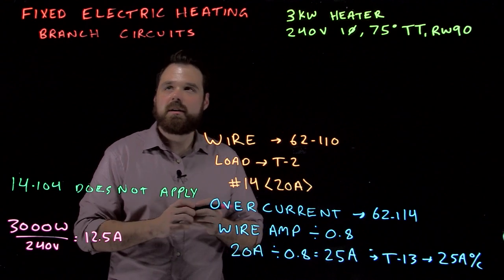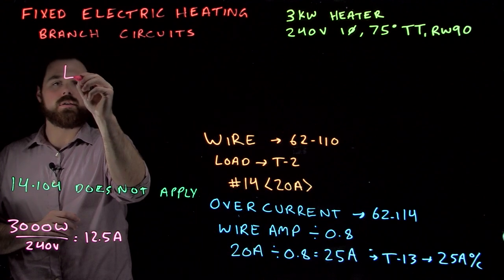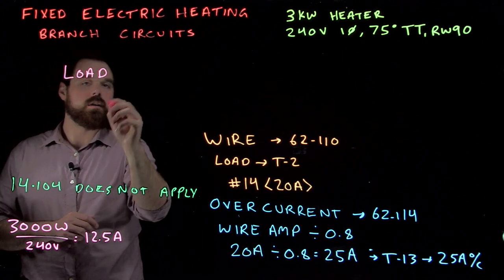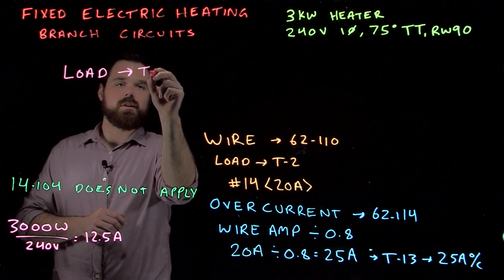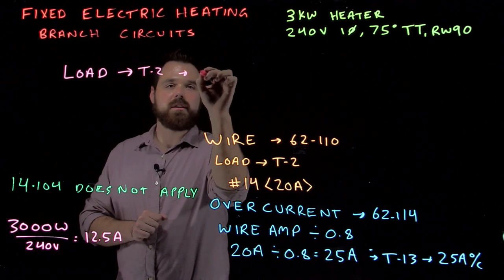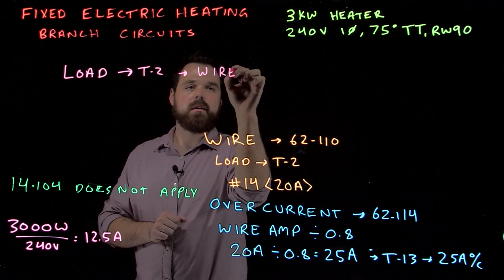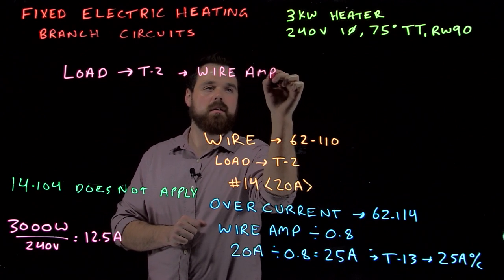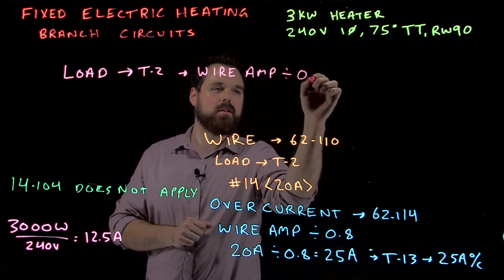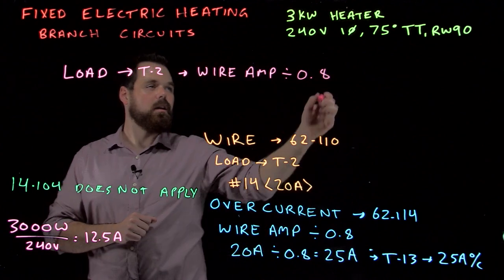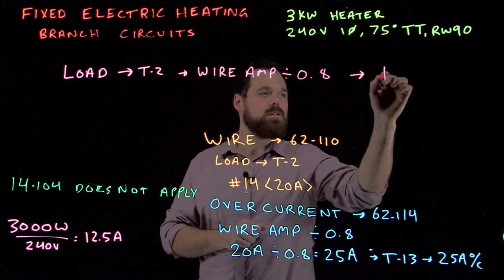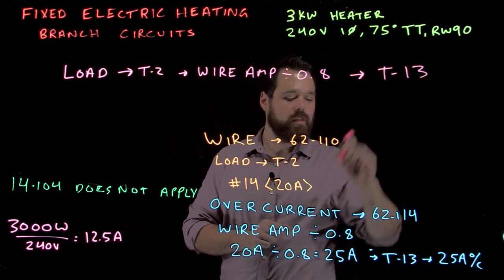So just a quick recap, you are going to take your load directly to table 2. Then you are going to take your wire ampacity divide by 0.8 and you are going to take that number to table 13.